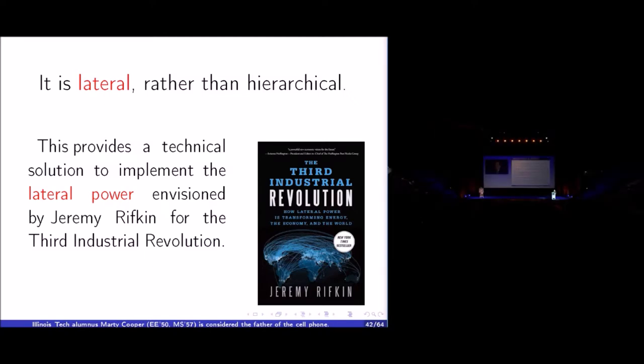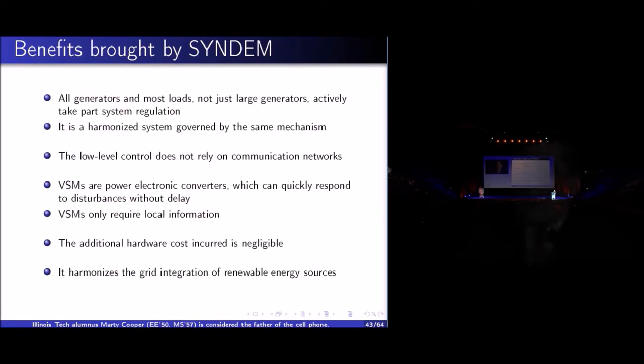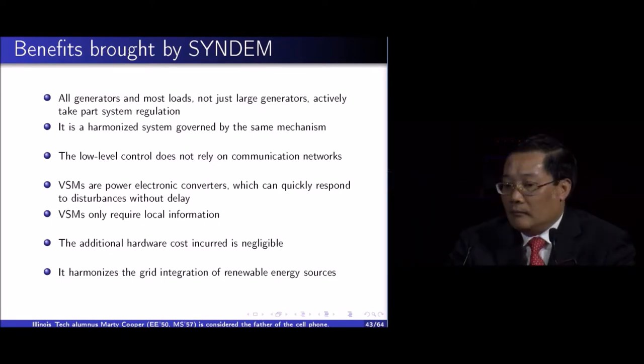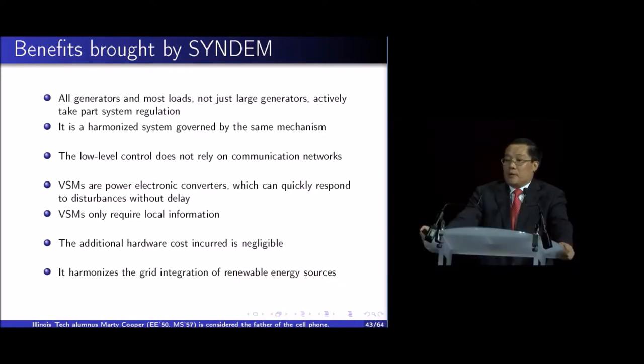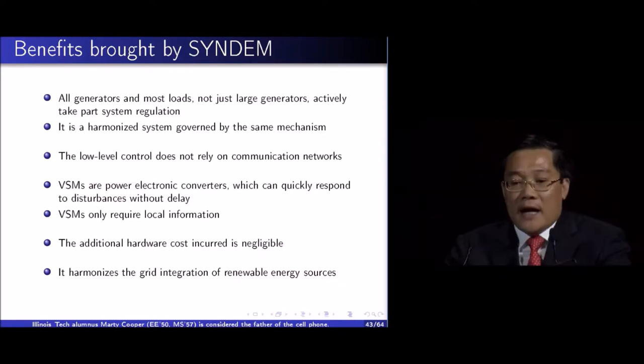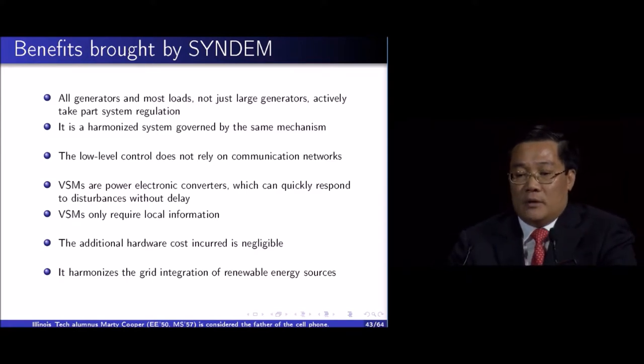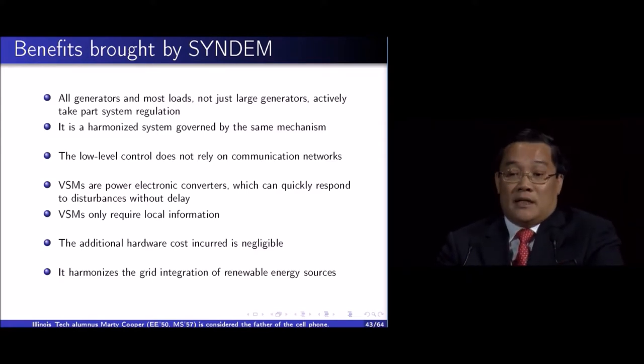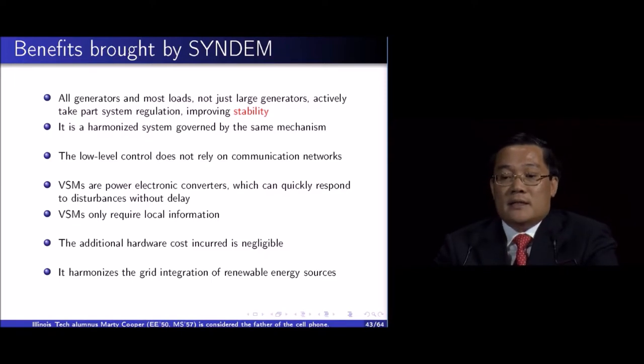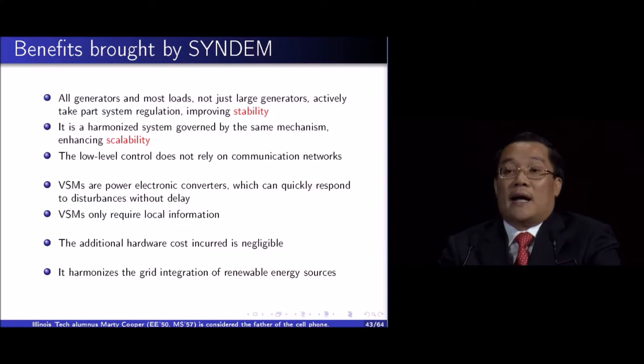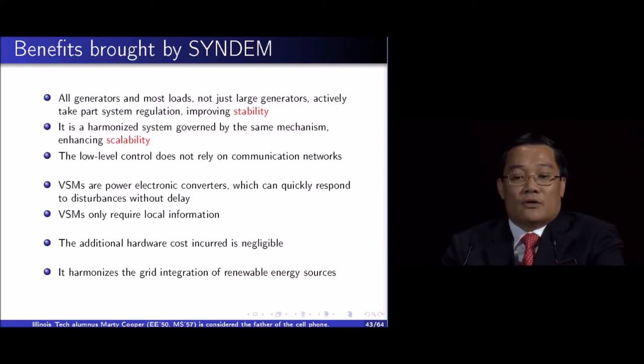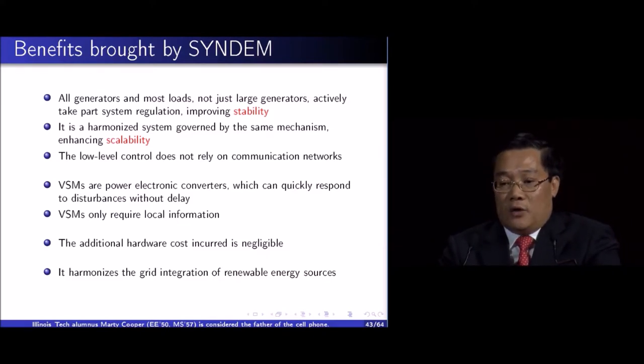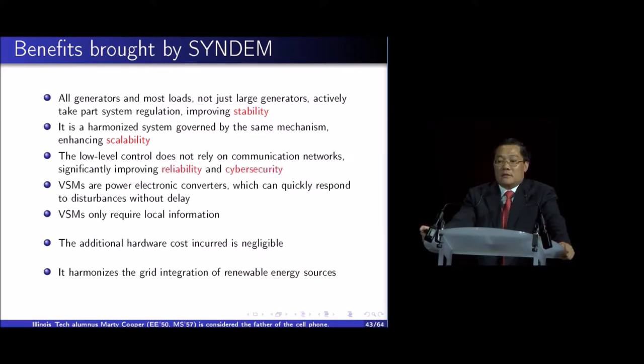There are a lot of benefits brought by the SYNDEM smart grids. For example, now all generators and most loads, not just the large generators, actively take part in grid regulation, so the stability is improved. This is a harmonized system governed by the same mechanism, which brings scalability. The low-level control does not rely on a communication network, which enhances reliability and cybersecurity.